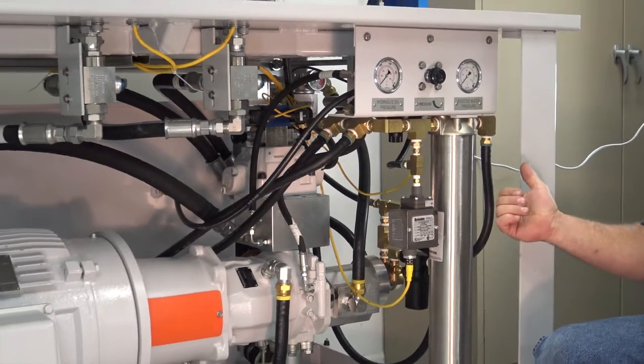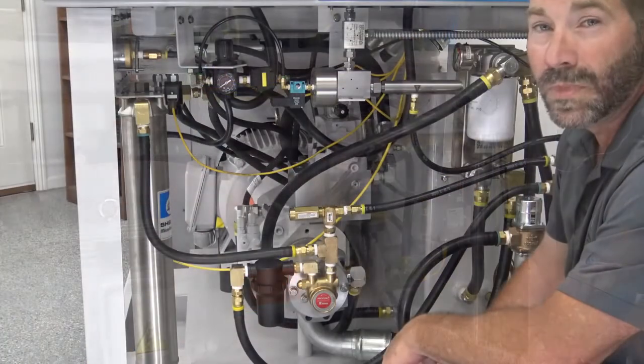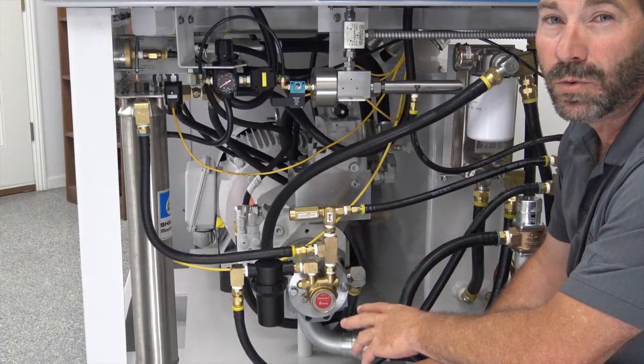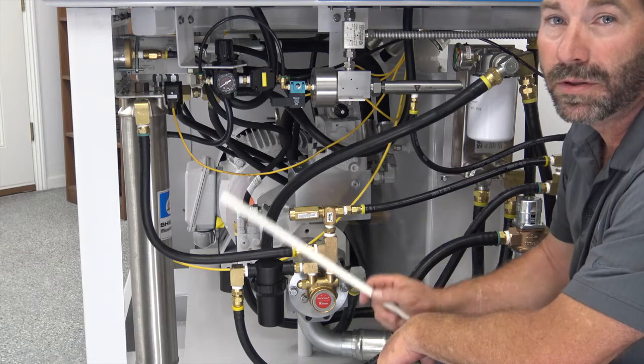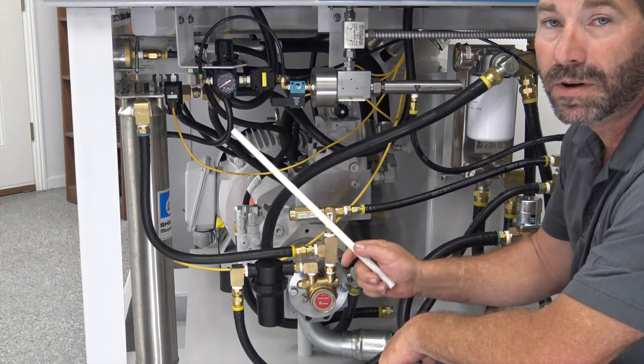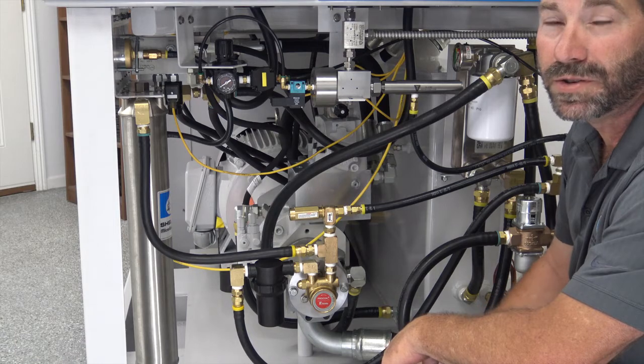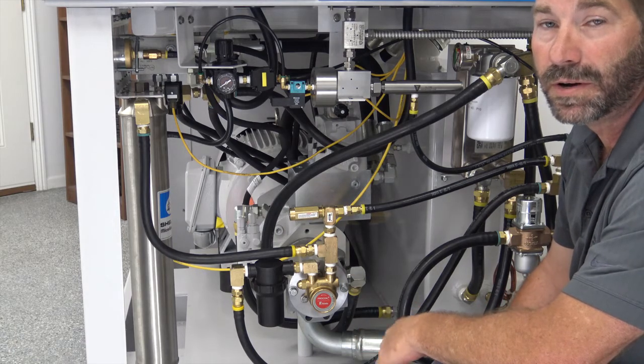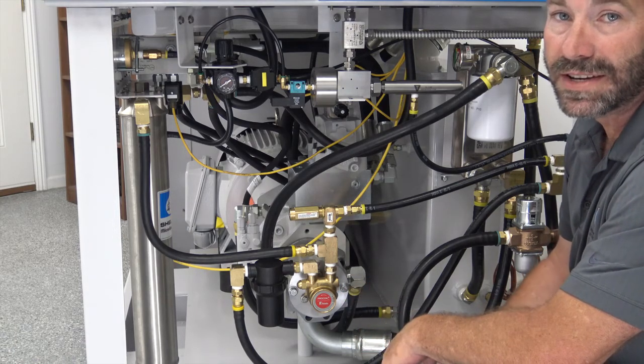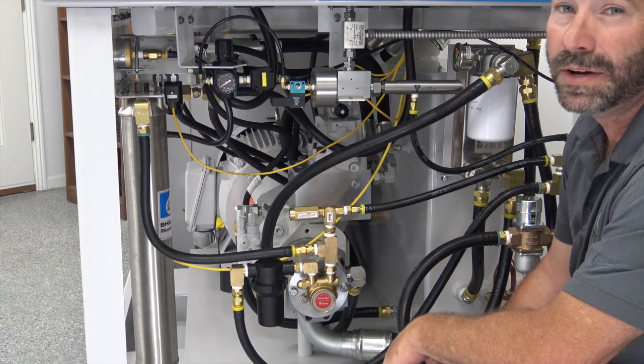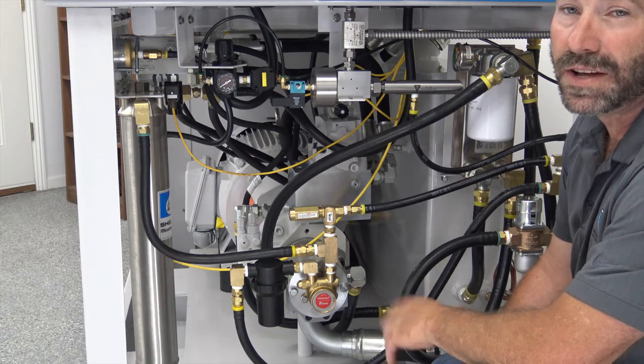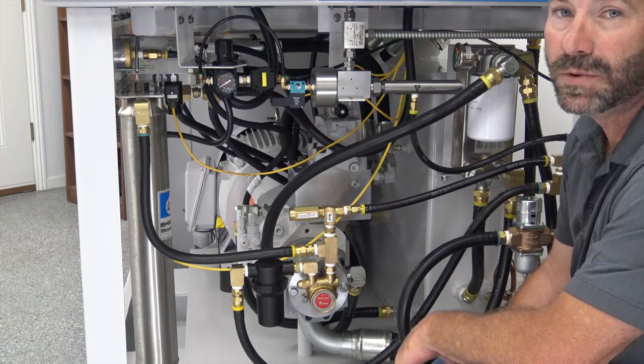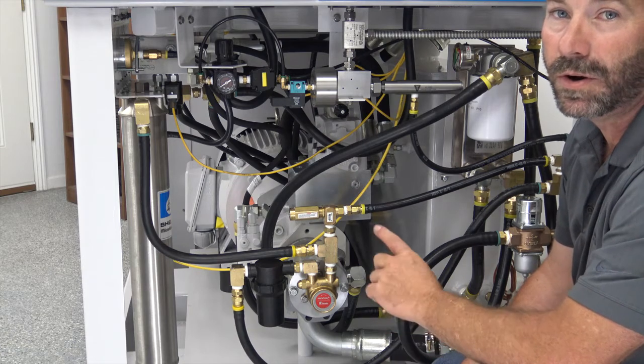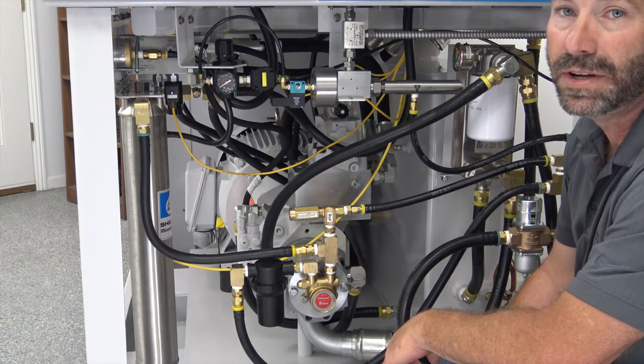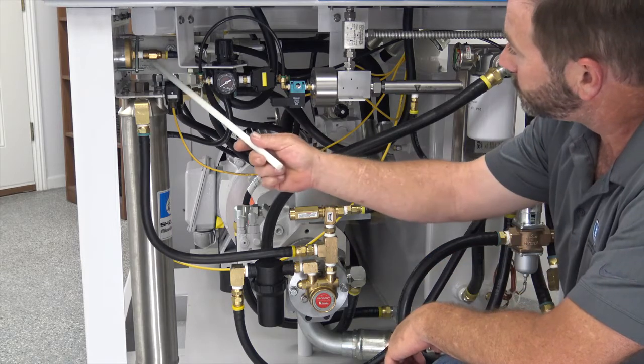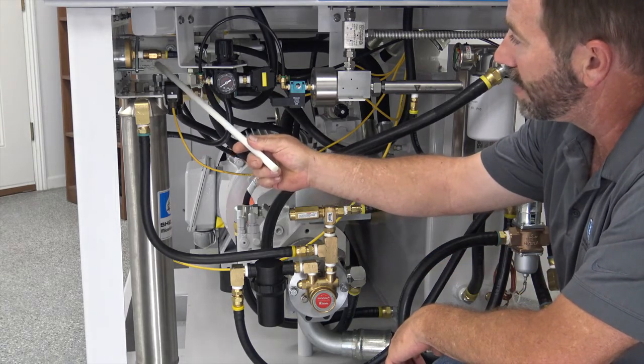We'll move around to the end and we'll start there. Okay guys, we're on the right hand side of the pump. Remember, on the front of the pump, the little black knob, the compensator knob, where you turn your pressure up and down, we always look at that as the front of the pump. Therefore this is the right hand side, or what's noted to be that way. There's a lot of stuff on this side of the pump. It's kind of busy, so we're just going to work our way through it, starting at the back of that compensator assembly. So up here in the corner you have the back side of the compensator assembly.